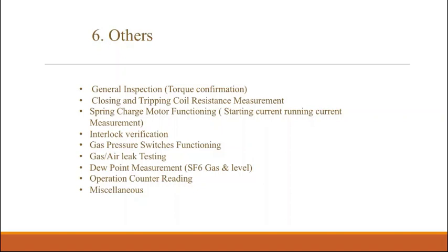Here I have taken miscellaneous tests. As I told, depending upon the voltage level, there are certain tests we are adding, like the 220 kV breaker will have a pole discrepancy test. The pole discrepancy test is nothing but if there is any fault in one phase, the other 2 phases have to be tripped. As I showed, in a 66 kV breaker all 3 limbs are operated by a single mechanism, but in 220 kV it is not like that. For individual phases, there is an individual mechanism.